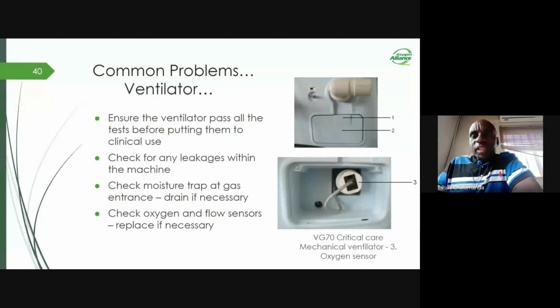Check oxygen and flow sensors and replace if necessary. Some ventilators have their oxygen sensors at the front of the machine. So they have like a directional arrow. So you just hold it and then you turn it toward the direction of the arrow and then gently pull it out and then replace it with a new one. Depending on manufacturers, usually 1 year is the period given to most oxygen sensors, that they have to be replaced annually. Or if not, then you can refer to the manufacturer's manual.